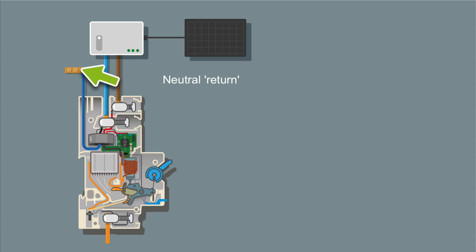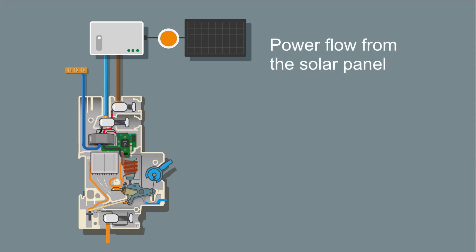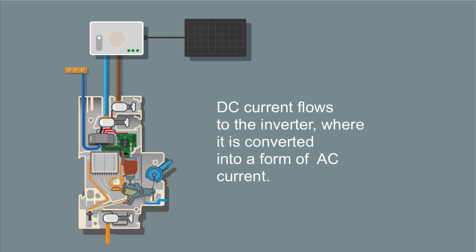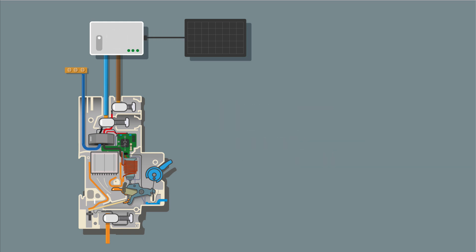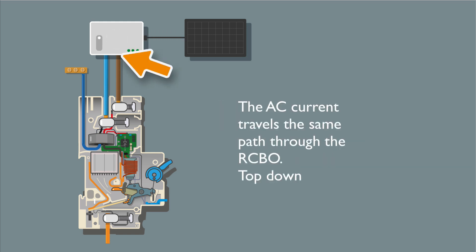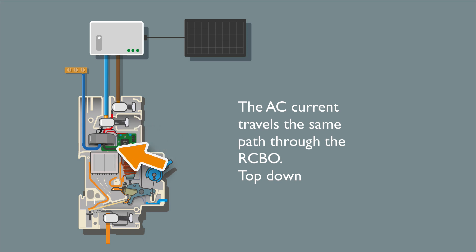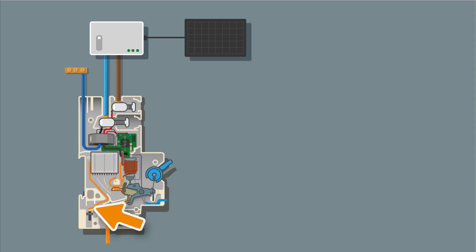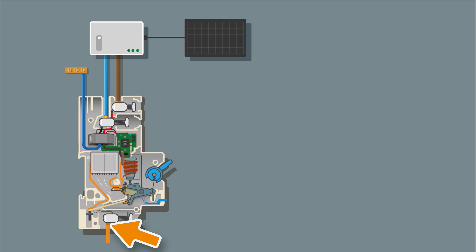And back to the neutral bar. Then we have DC current which flows from the solar panel to the inverter. This DC current is converted into a form of AC current, which returns back down the line connection, through the load connection, back through the toroid, through the solenoid, back onto the moving contact, in the operating mechanism, back down the thermal overload, and onto the bus bar connection. Exactly the same path — it's just doing it top down.